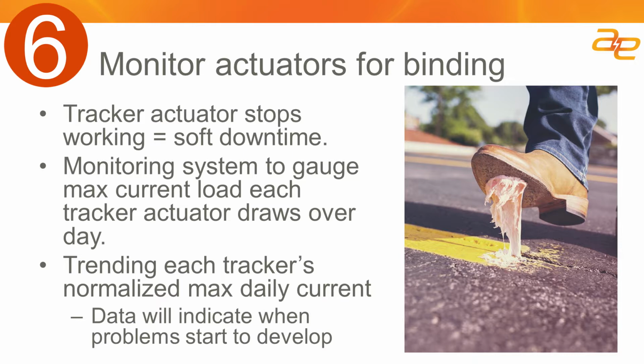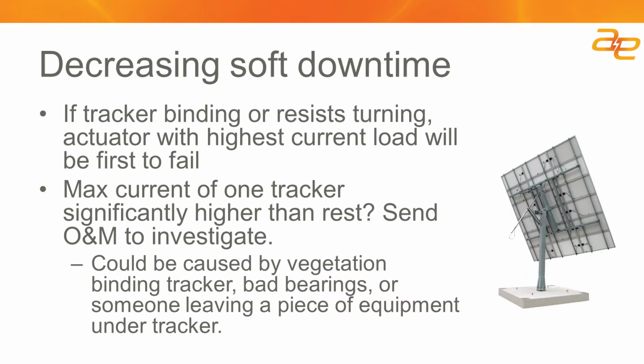In normal operations, the tracker actuator demanding the highest current should change from one table to the next over time, so if it's moving around the site, that's normal. But if you see the same tracker having a high current draw over and over again, that's probably indicative of some binding, which could come from a number of sources. In the southeast I see quite a bit of vegetation, vines and grass growing into the mechanical structure of the tracker causing binding, or it could be bearing wear, or something as simple as equipment left in the field impeding smooth operation. All of those are a trigger to roll someone from O&M to investigate, and knowing exactly which tracker actuator has the problem saves a whole lot of time and money.